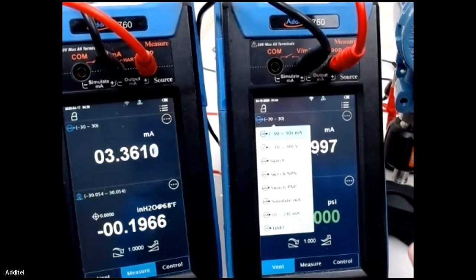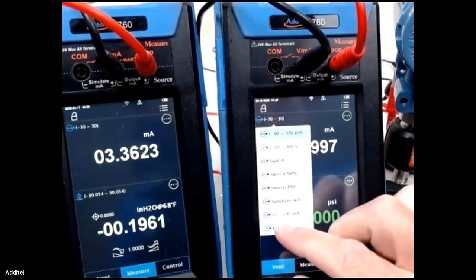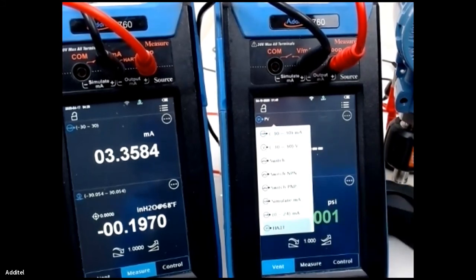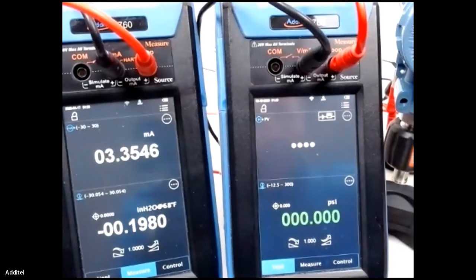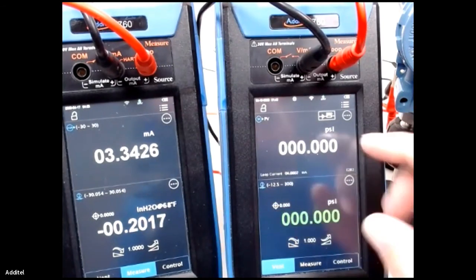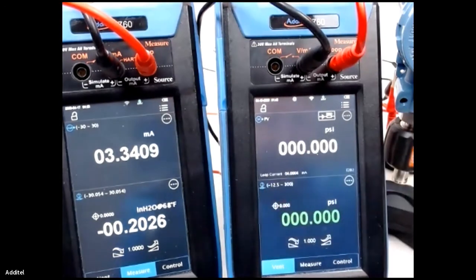I don't think those are probably really easy to read, but what we're going to do first is a HART transmitter. I've got this unit dropped down, and I'm going to select this HART transmitter, and it's going to go out and look for it. Once it finds it, it pulls all the information in, and we can see what's going on here. We've got our loop current down here, we've got our pressure, and we're reading the HART transmitter at this point.